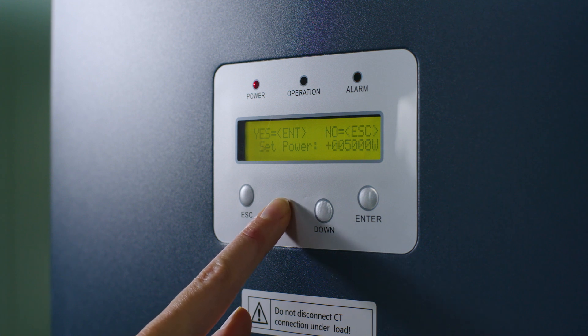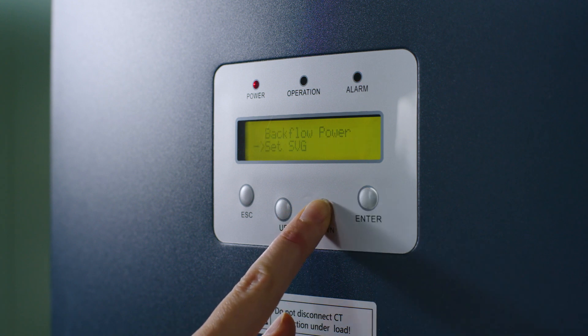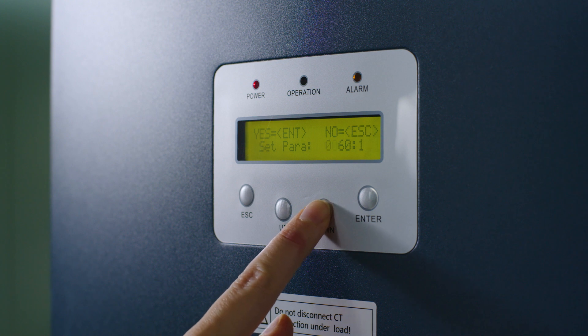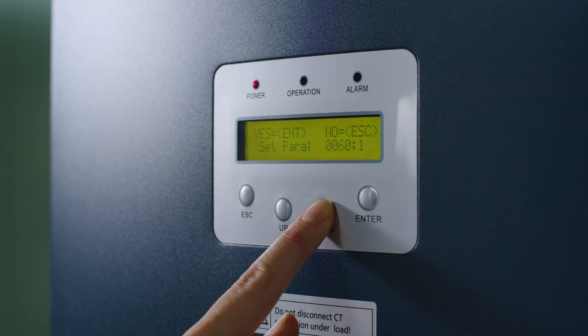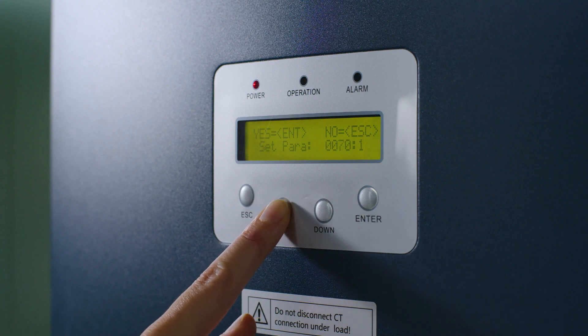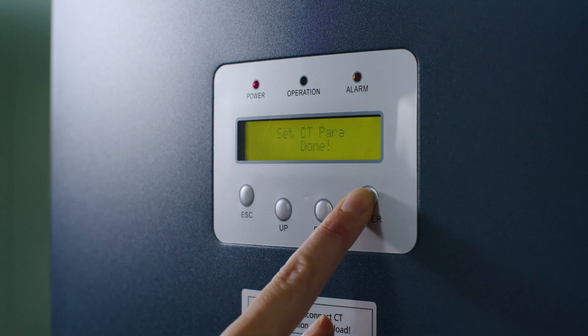Set the transformer ratio of the current transformers. Choose Set CT Para and fill in the CT Ratio value. Be aware you can only change the primary value. For a current transformer with a ratio of 150A to 5A, the ratio is 30 to 1. Press Enter.